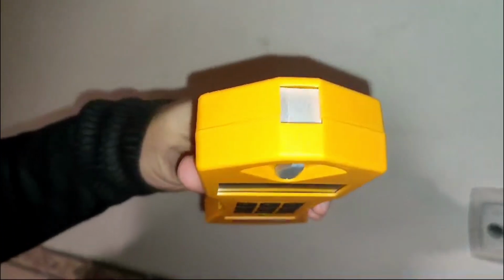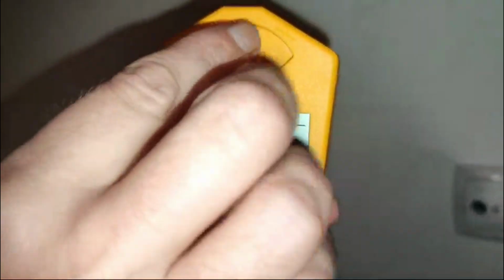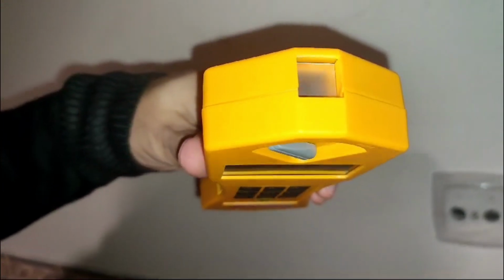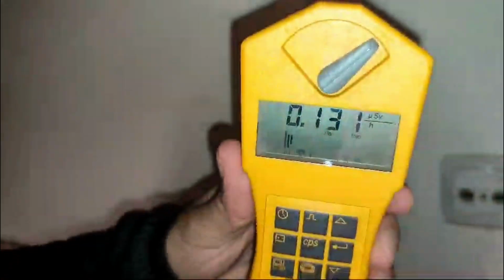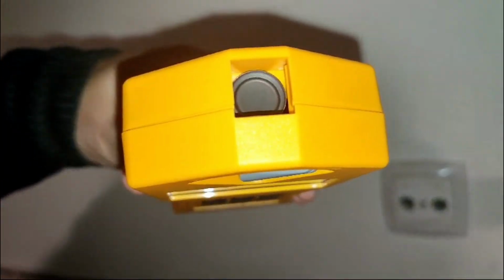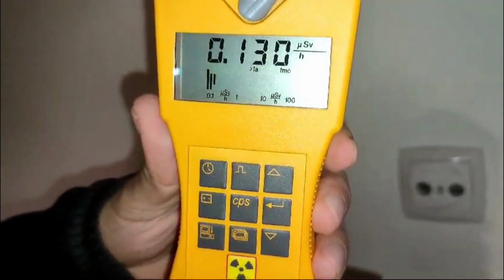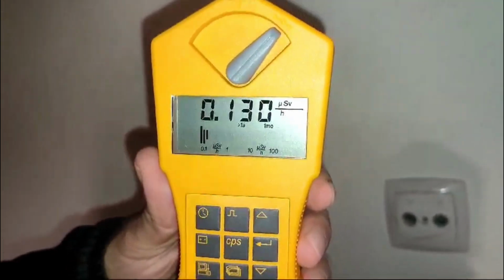When switching the filtration to measure other radiation types, such as alpha or beta particles, some devices do not automatically change the reading unit, as the filter switch is not electronically coupled to the unit display. Users must manually select the appropriate unit of measurement when measuring weakly penetrating radiation. Otherwise, readings will be in dose rate.